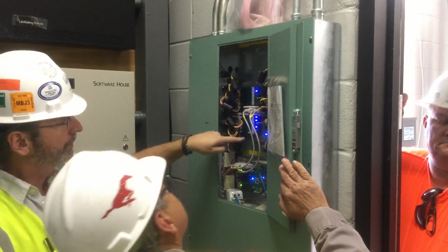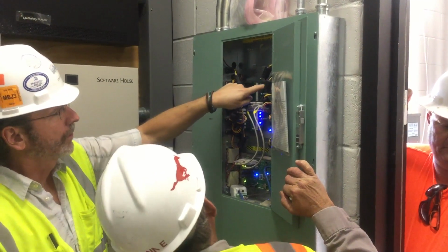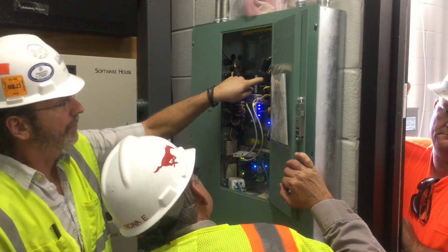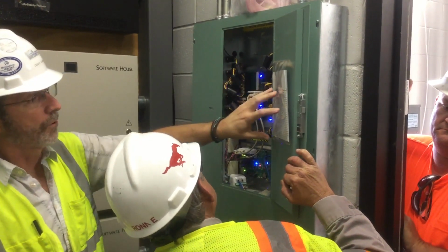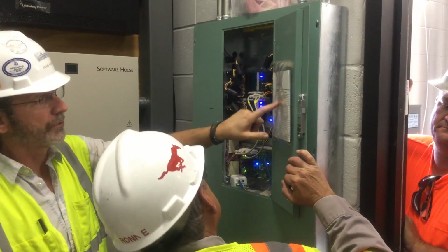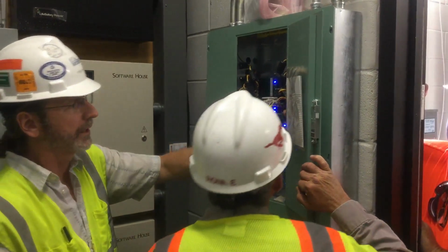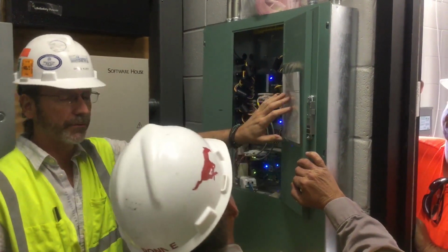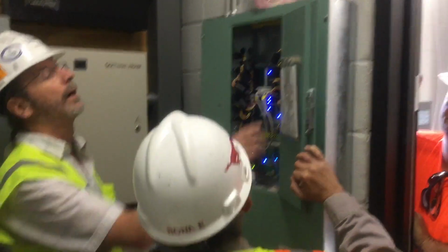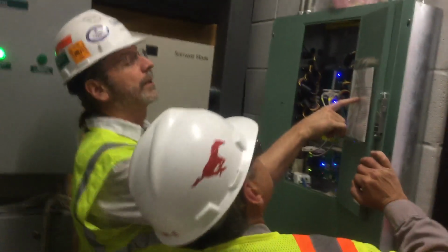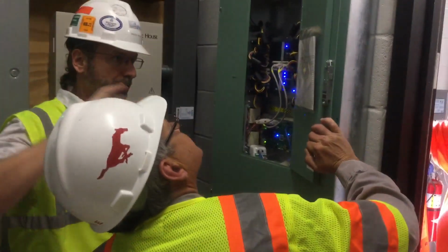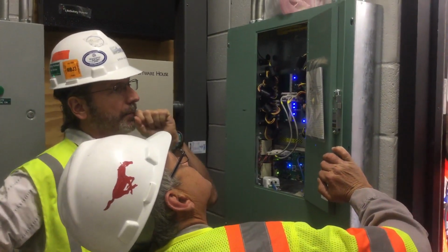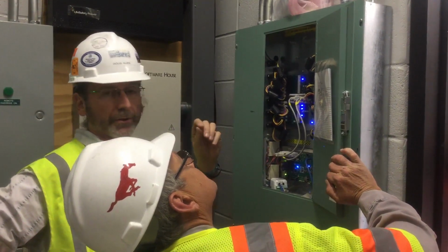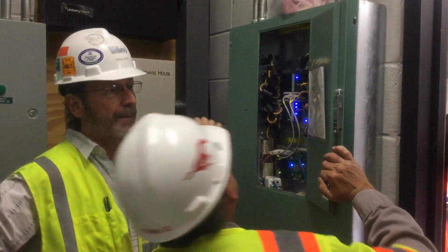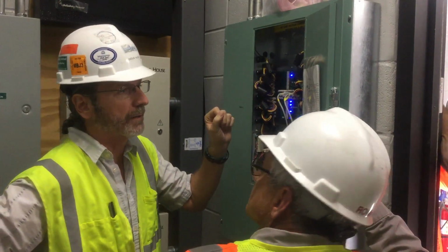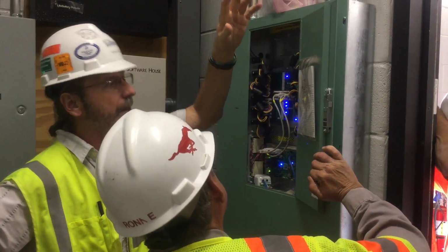Notice here I've got these 12 indicator lights where you can manually actuate a relay on or off with these buttons. In the door is a relay panel schedule that tells you what's assigned to each relay—there are really only about 6 or 7 relays in use on this panel. A couple of them feed miscellaneous branch circuits into the building, and on many of those circuits there are occupancy sensors or timer switches, so these never need to be turned off because it's managed automatically.